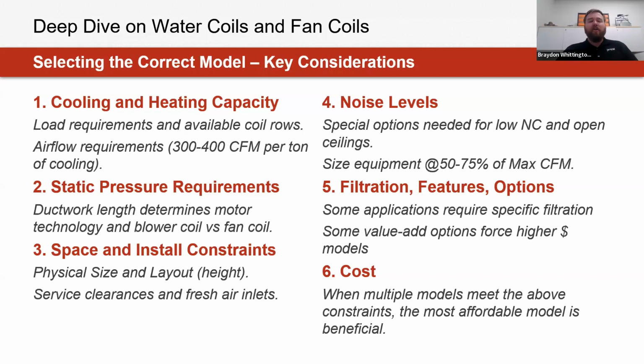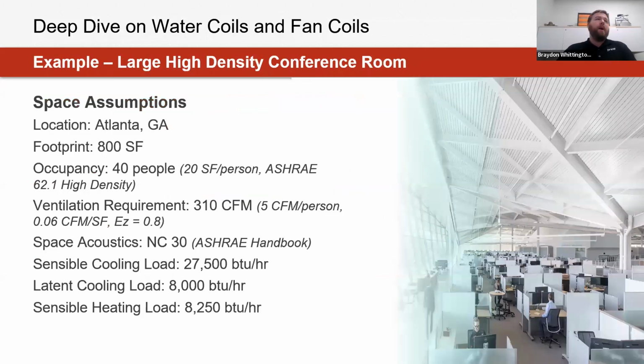But that gives us a good framework, especially as we start to look into this case study, keeping all those variables in mind. So here's the example in terms of some of our assumptions that we're going to be using for this office space within this given setting. Essentially, we have a footprint of 800 square feet, and a certain number of people that are going to be within this space. So being able to address our ventilation requirements based off of a certain square footage, as well as ventilation requirements based off of the number of occupants.